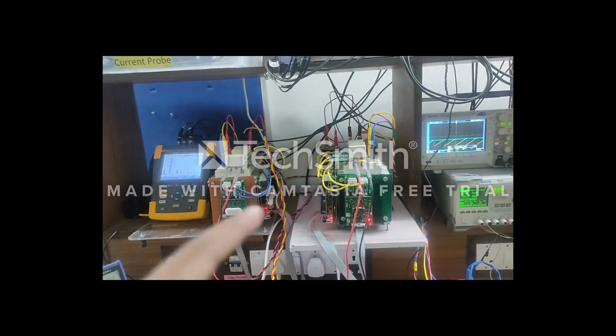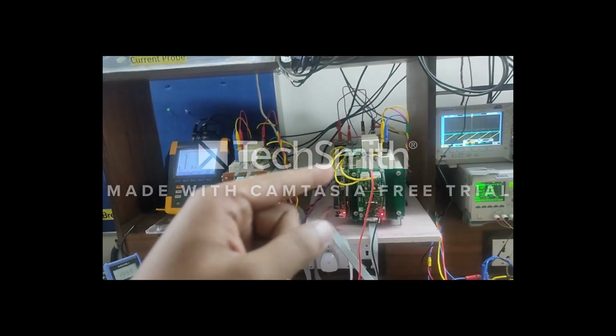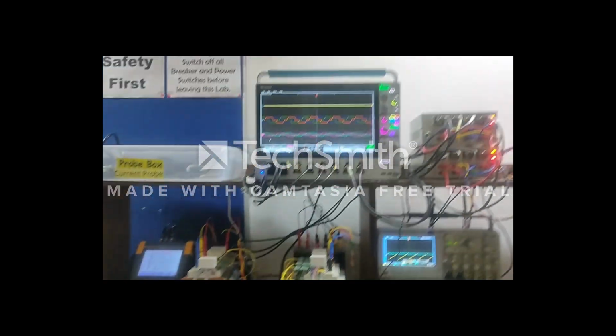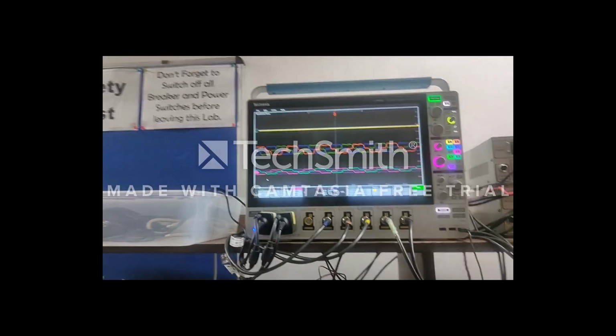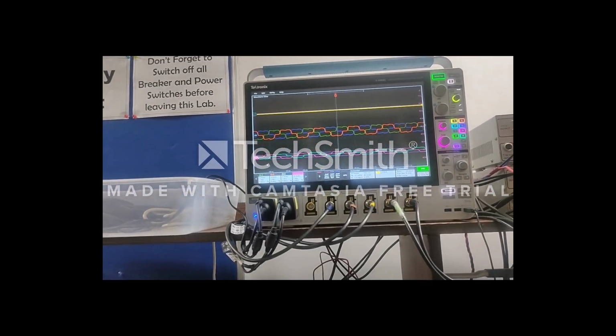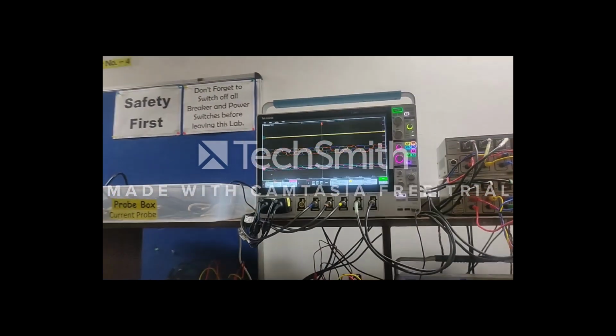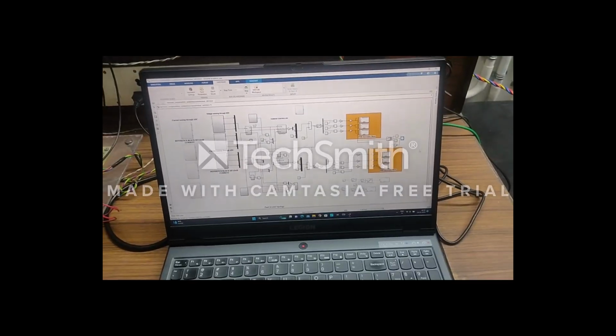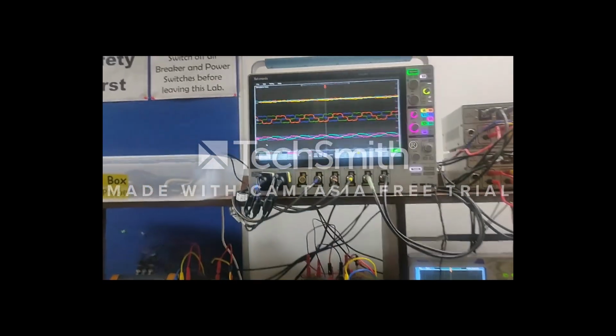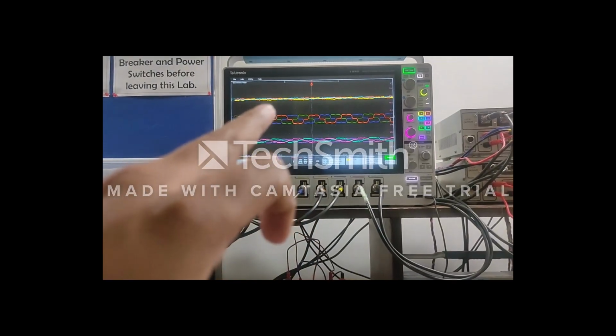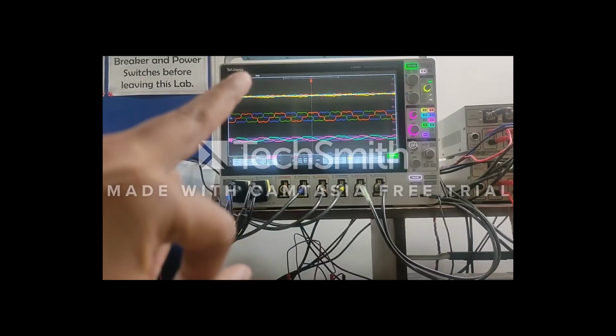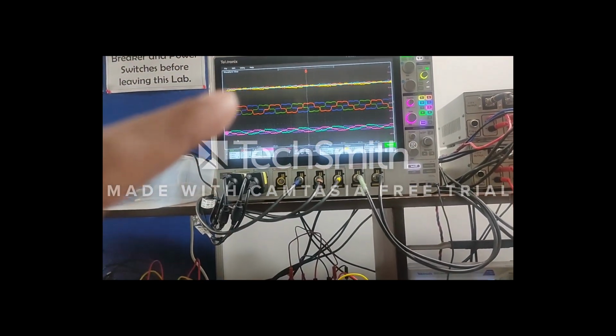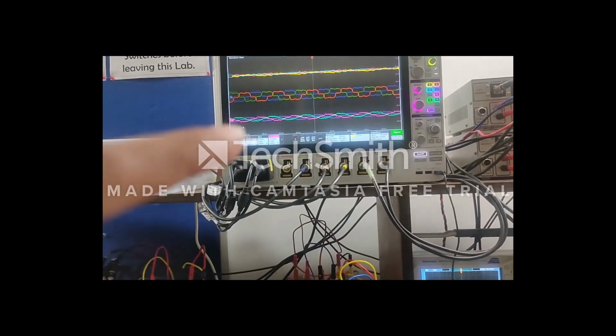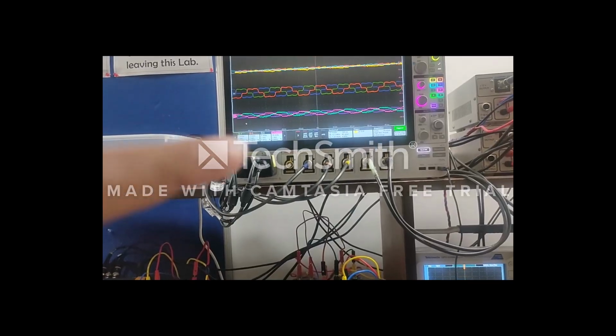So whatever the available power at the solar inverter, the first inverter source, will be injected into the grid and load. So this is the non-linear load drawing power from the grid. The shape of the current is non-sinusoidal, as seen in mode 1 and mode 2 operation. So now we turn on the pulses to both inverters. You can see the current shape has changed to sinusoidal, and the harmonics are being compensated by the inverter. The available power at the sources is lesser than the load power, so the remaining power is supplied by the grid to the load.